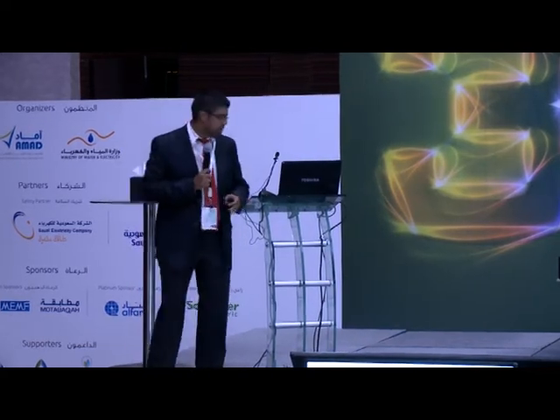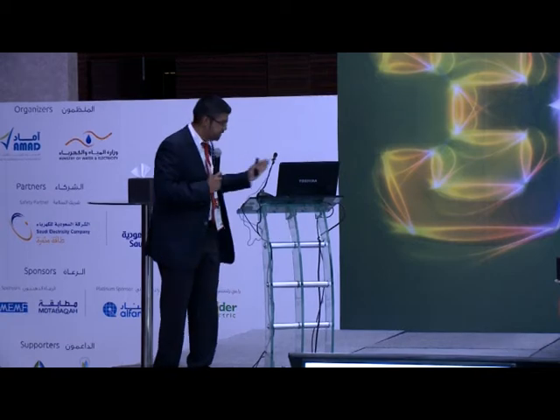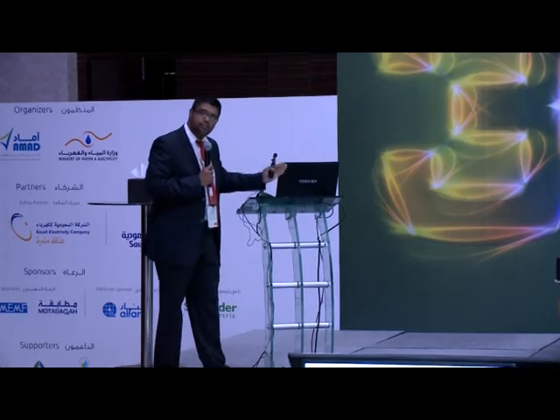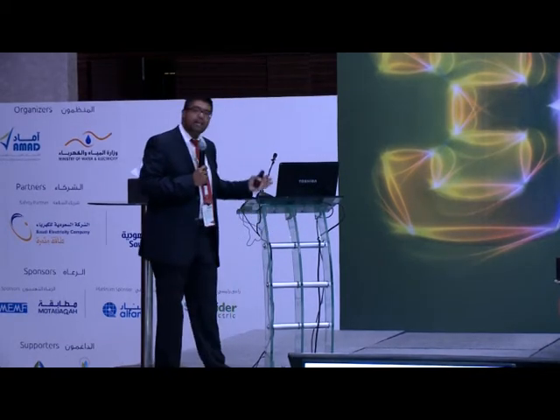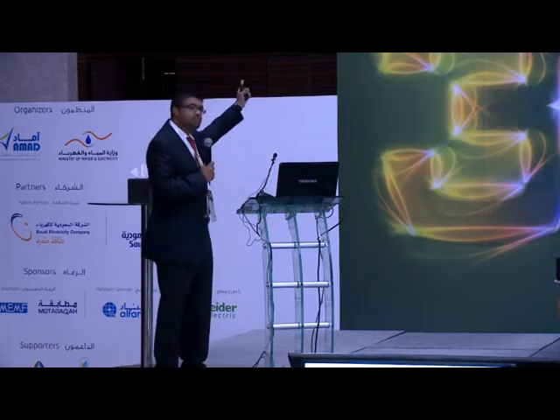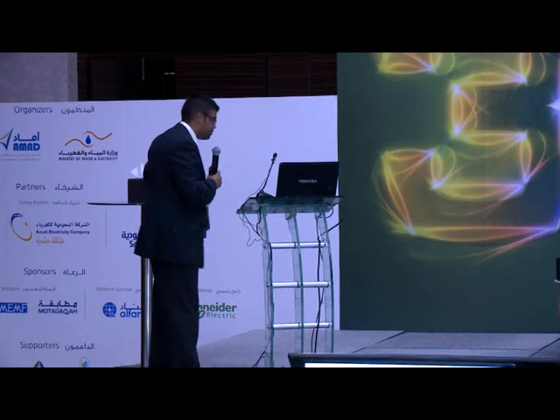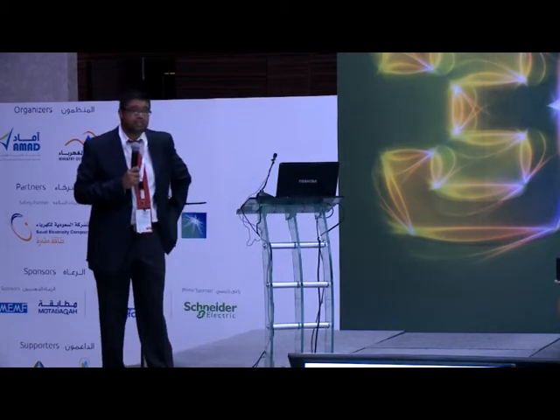If an arc were to occur at this particular region, let's imagine that this is an electrical panel, and if an arc had to occur on this panel, the arc energy is a function of the system energy, the system fault current. I saw a presentation earlier which spoke about voltages and boundaries. And I tend to challenge that because the predominant factor with regards to arc flash energy calculations is fault current. And specifically, IEEE 1584 refers to steady state bolted fault current.